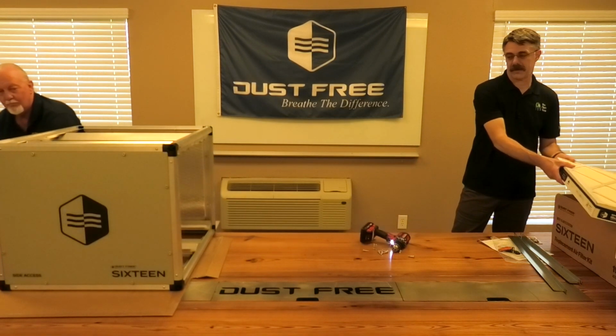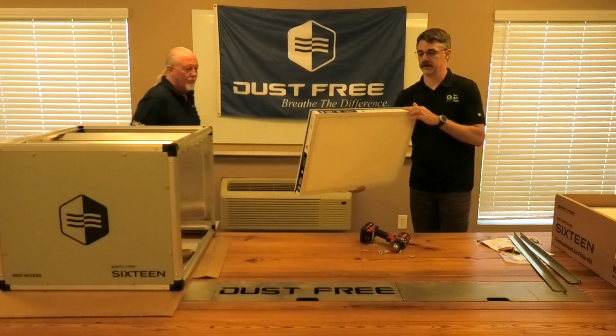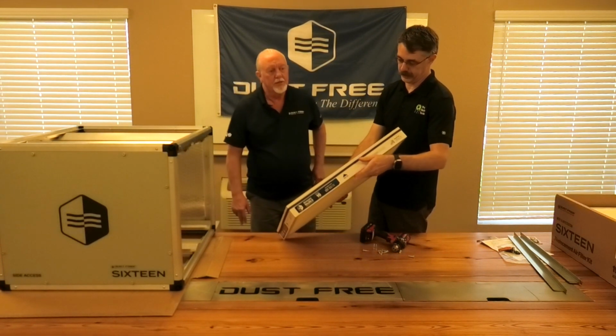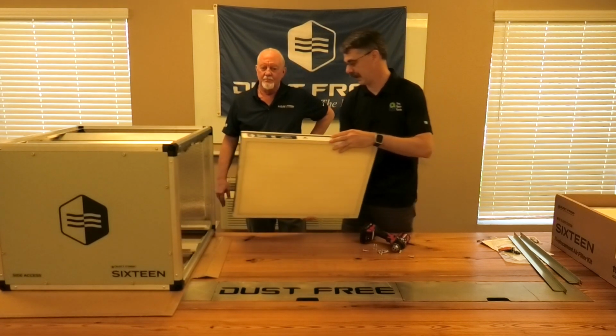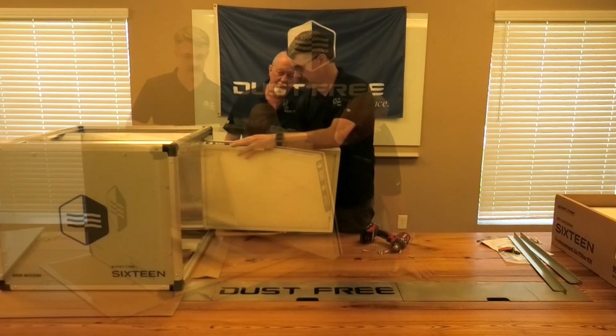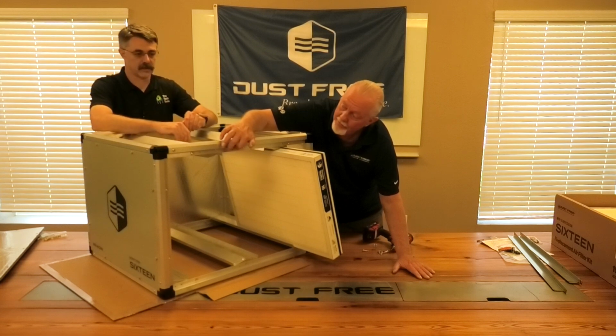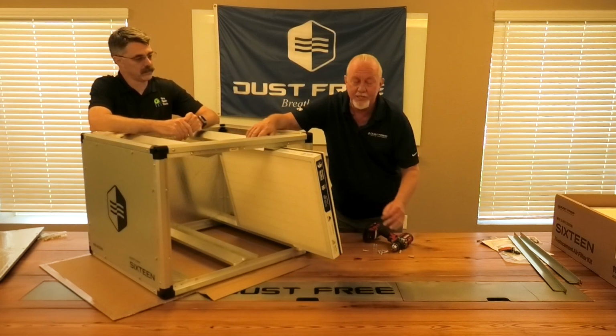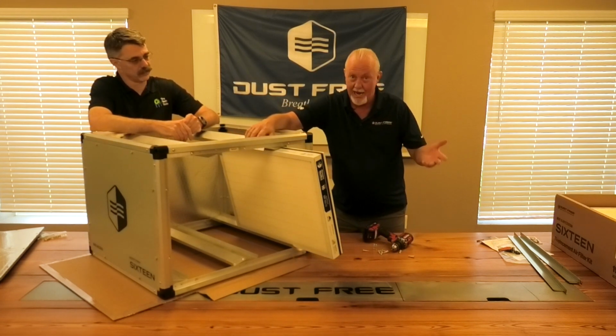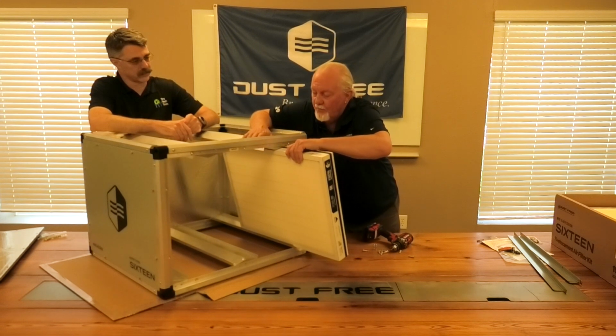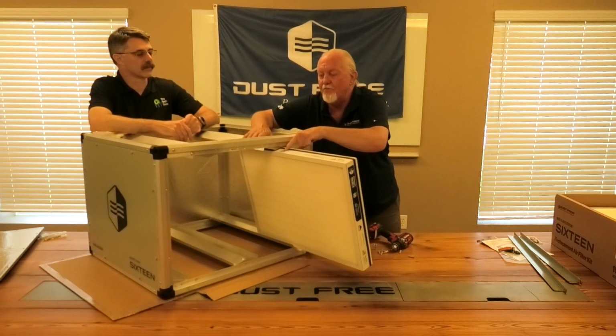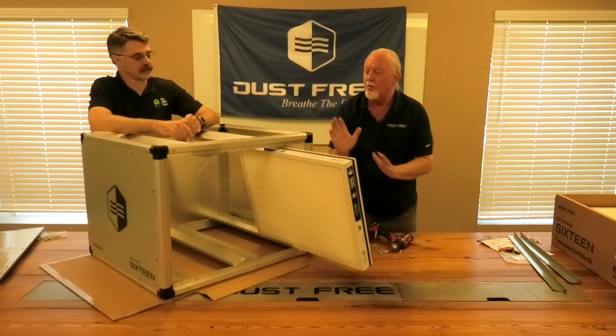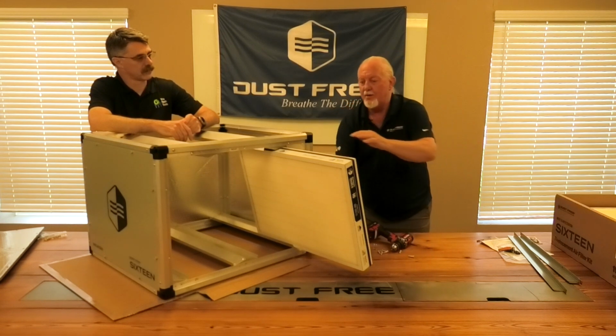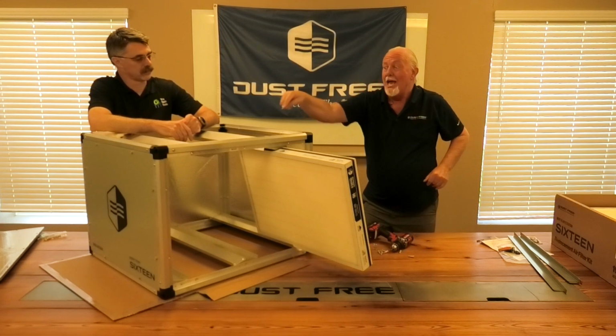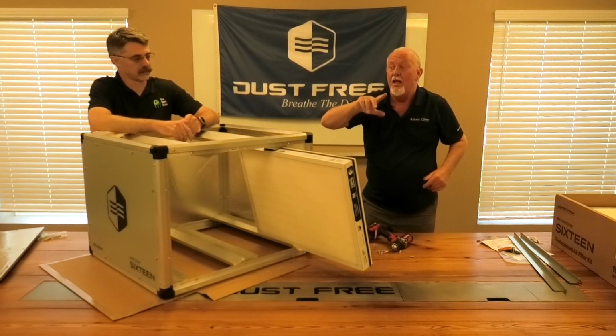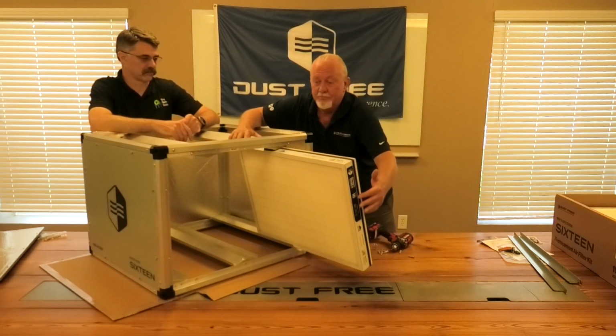So when we talk about putting filters in here, I want to look at the airflow on here. We've got our nice gasketed filters. This is the outlet, so that means the arrows need to be pointed towards the outlet. If you back this filter out, you'll see airflow is pointed this way. Because this is a V-bank, airflow is going this way towards the outlet. That's how you know you're putting them in right.